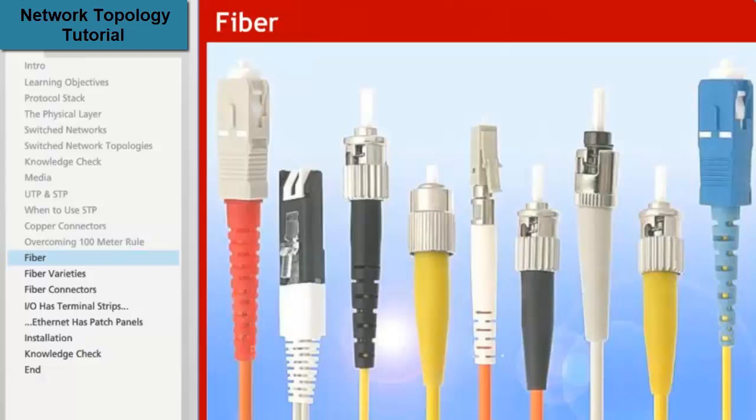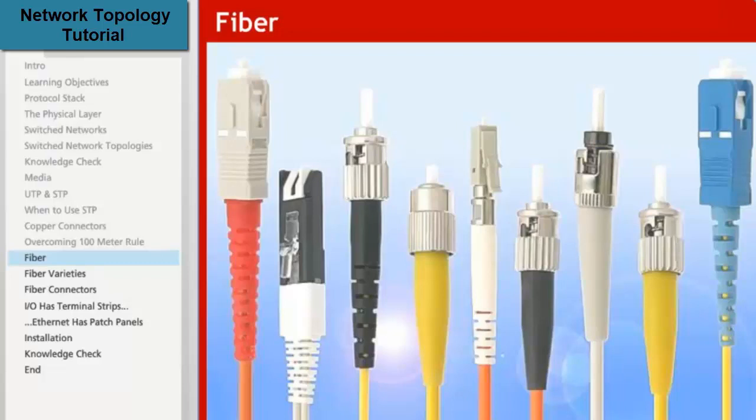Rockwell Automation recommends that fiber always be used for switch-to-switch communications instead of copper cable. One of the reasons is that the network convergence time, or the time it takes a resilient network to recover from a disruption when using resilient protocols like STP or REP, is much faster with fiber. Fiber also is immune to electromagnetic interference, making it perfect for noisy environments in addition to long runs.